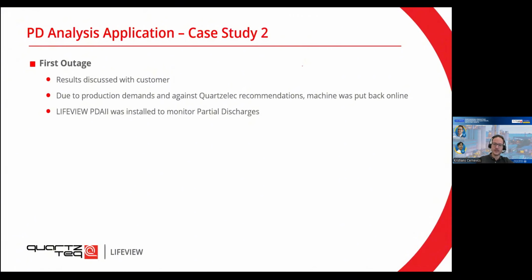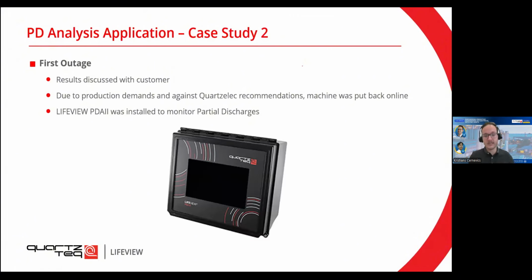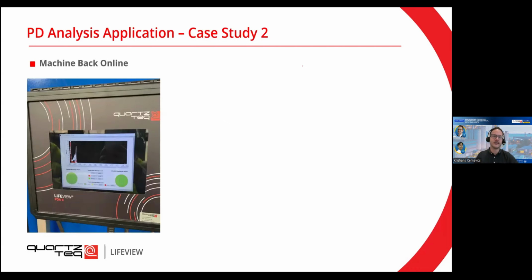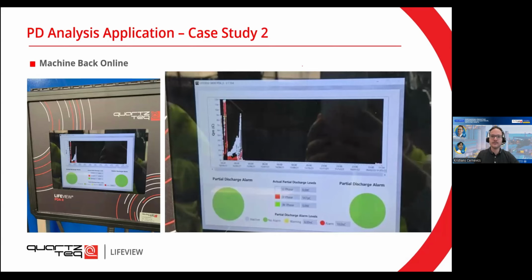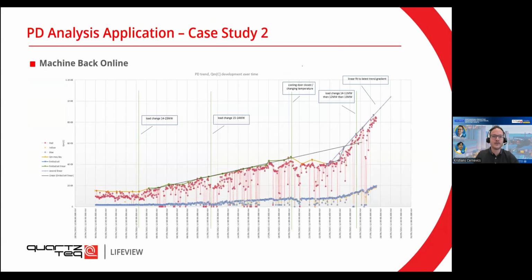And here I can show you the real benefit and the strength of this online monitoring, of permanent online monitoring. So the machine was put back on, and this is how the trends start to look like. And if you see on the second screen, the white part is increasing very, very fast, like an exponential. And here, what you can see is that for a couple of days, it kept increasing until the very last week. It was like a huge shoot up, essentially, on the partial discharges.